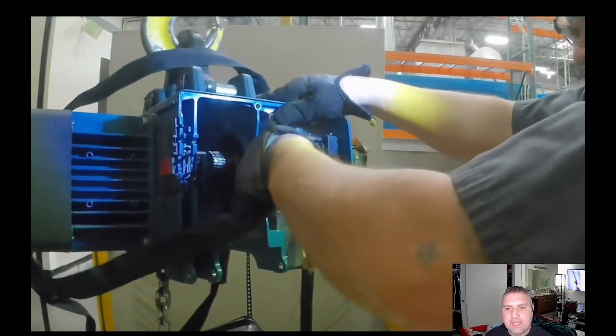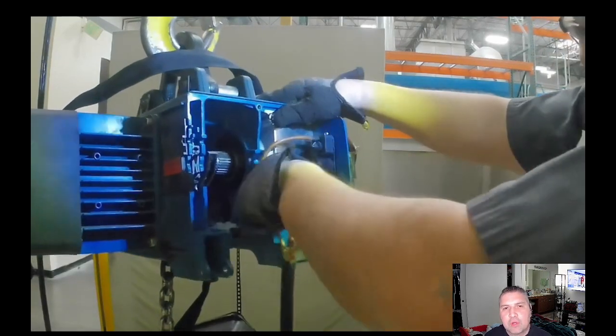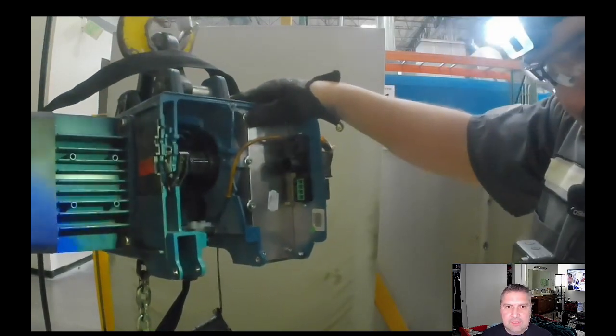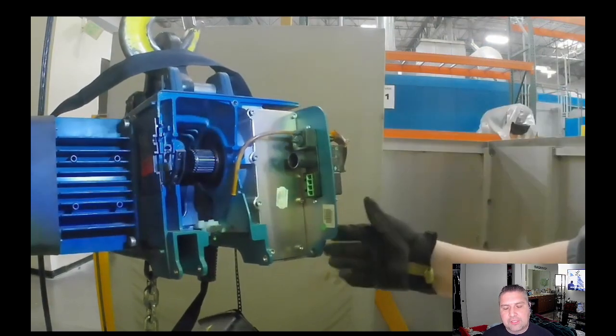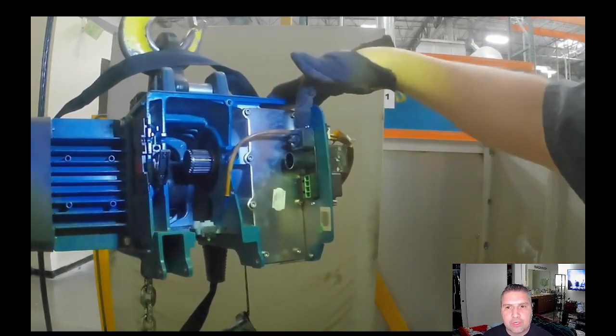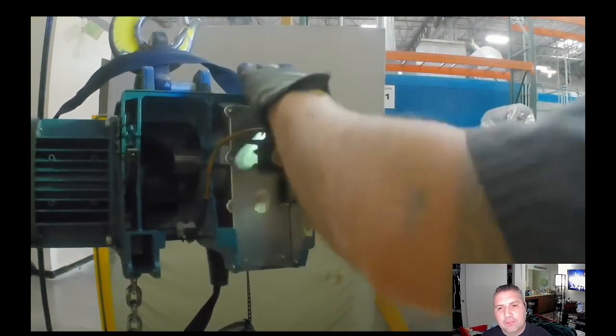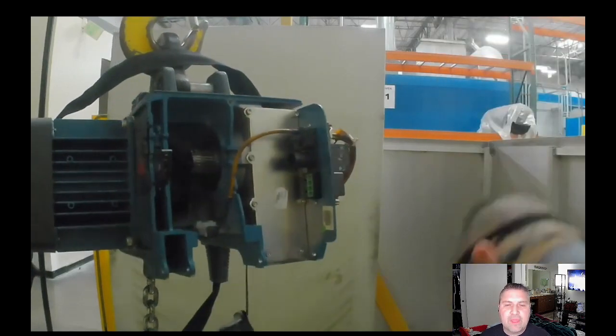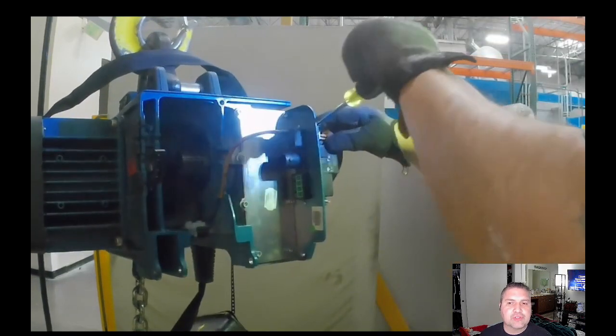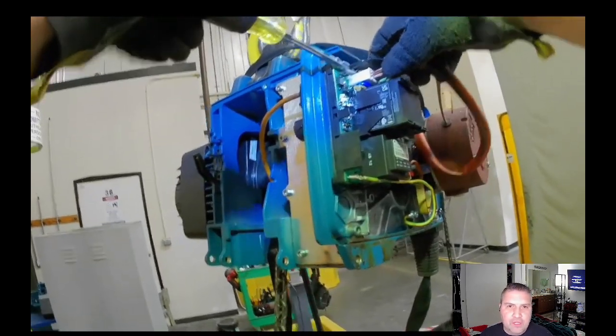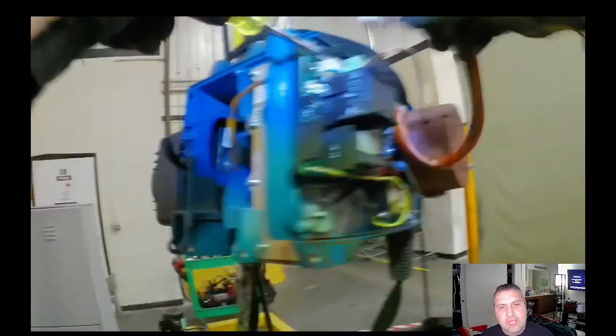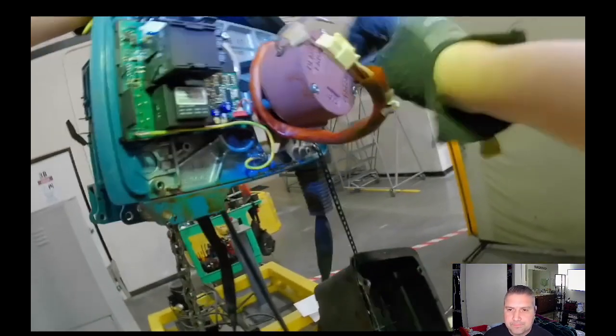So it gave me an idea like, hey, if the motor's not even getting the voltage that it needs, there's probably an issue in the control board. And that's all these hoists mainly run off of, a control board that has inputs and outputs. So if the main function of the control board goes bad, it won't deliver that input into the output into the motor.